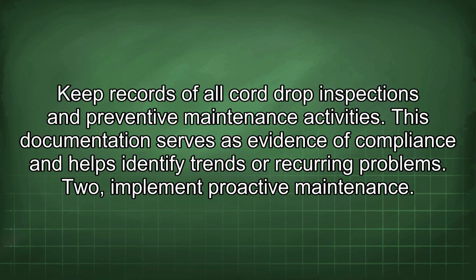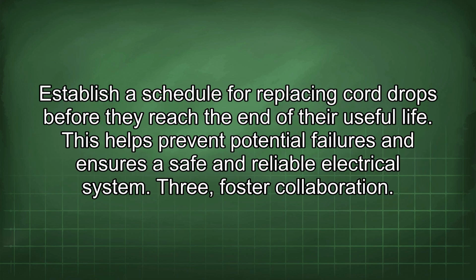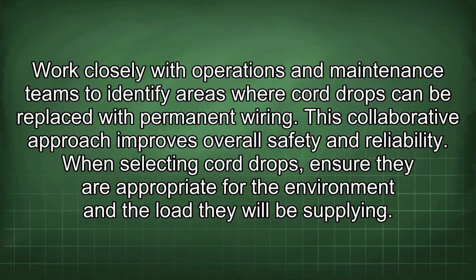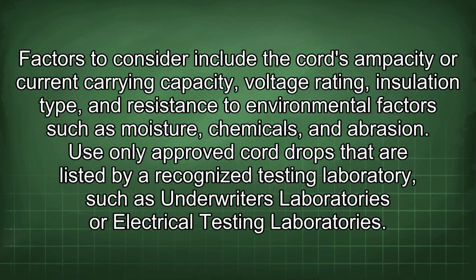2. Implement proactive maintenance. Establish a schedule for replacing cord drops before they reach the end of their useful life. This helps prevent potential failures and ensures a safe and reliable electrical system. 3. Foster collaboration. Work closely with operations and maintenance teams to identify areas where cord drops can be replaced with permanent wiring. This collaborative approach improves overall safety and reliability. When selecting cord drops, ensure they are appropriate for the environment and the load they will be supplying. Factors to consider include the cord's ampacity or current carrying capacity, voltage rating, insulation type, and resistance to environmental factors such as moisture, chemicals, and abrasion.